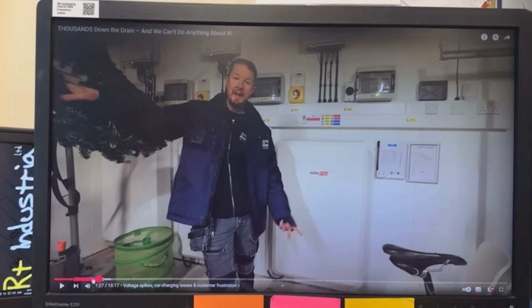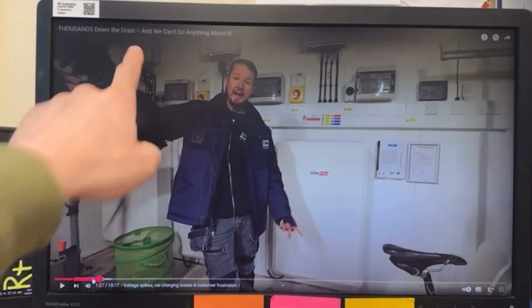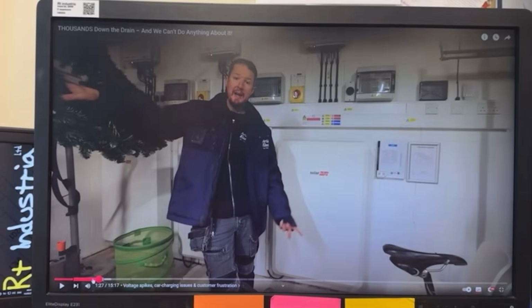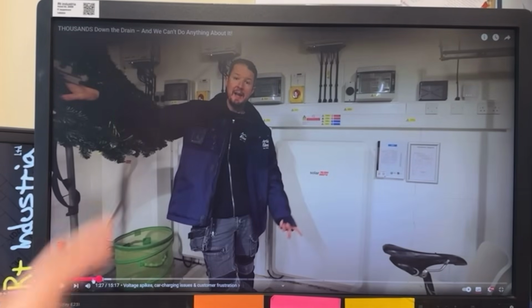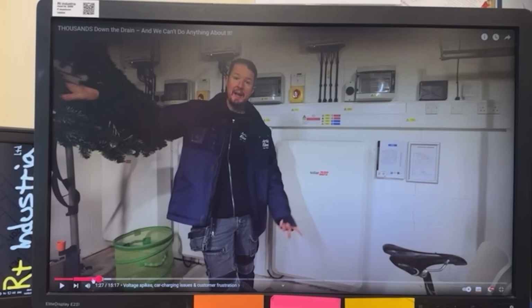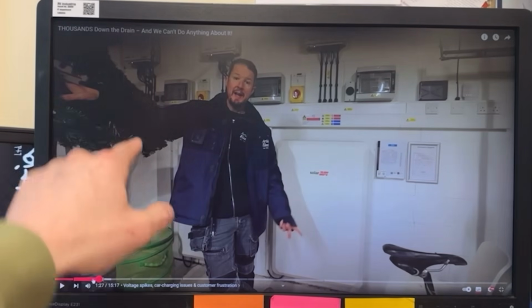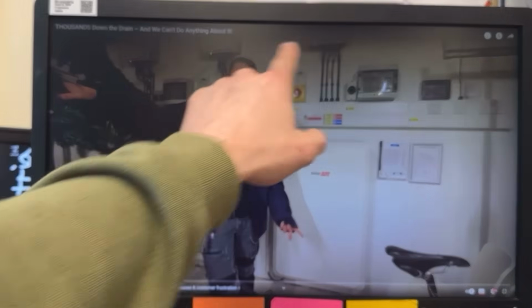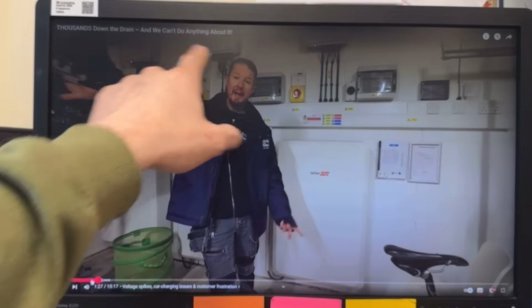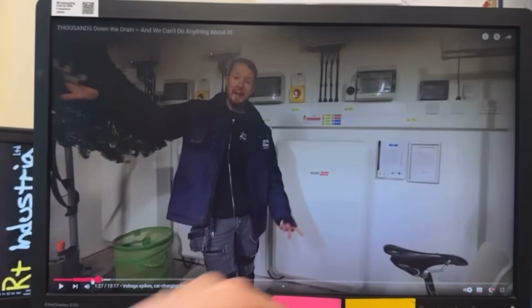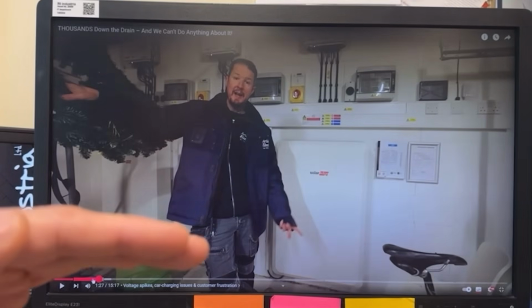DC coupled batteries. Okay, so one of the problems I identified, I put it in the comment of the video, is 3 inverters ramming it out to the grid when it's a sunny day. To get the voltage to go out, the voltage needs to be higher than the grid voltage. But my thought is, these will fight each other. Although they are interconnected, as was corrected, yeah, they've got to send commands to each other to do the voltage thing. But if one of them makes the voltage rise a little bit, the other will have to rise to make do with it, the other will have to rise, and so on.